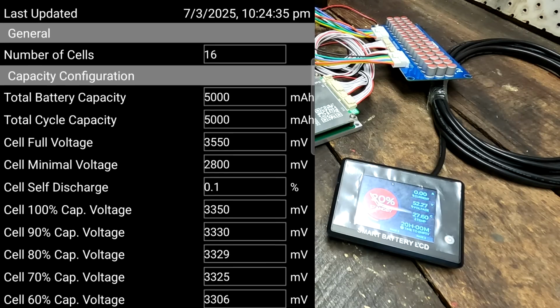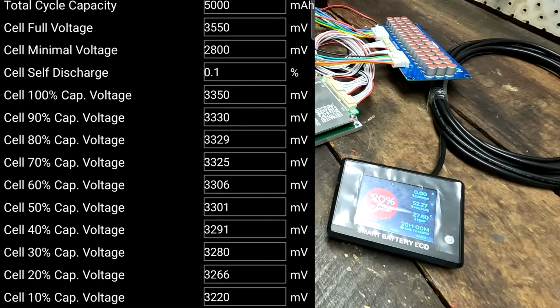Then we have a whole bunch of voltages we can set here: cell full voltage at 3.55 and cell minimum voltage at 2.8. I think these are the two parameters actually determined when the BMS resets to 100%. Also these voltages here for each 10% of capacity, we can set individual voltages for that. It's not really useful for lithium iron phosphate because of the very shallow charge and discharge curve, but if you have lithium ion or LTO batteries, you can set these voltages to match your percentage, so the BMS has a very good understanding of what state of charge you're on.